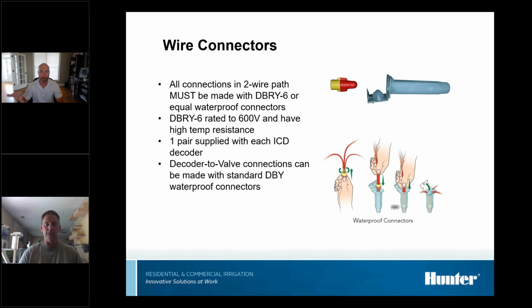The reason that's so important is, remember, we're not just sending voltage down this 2-wire path, we're sending communication, and the wire path is always hot, constantly pulsing. That's why we require 600 volt connectors even though this is only a 30 to 35 volt signal: the constant pulsing and communication will degrade a regular run-of-the-mill wire splice over time. I've seen wire splices taken apart that were burned black because they weren't DBRY6.